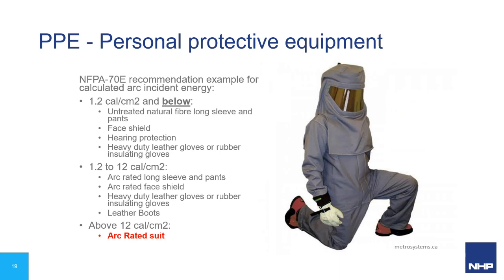And then above 12 calories per centimeter squared, it's talking about arc rated suits like what you've got on the right hand side there. Due to the comfort, the cost of the suit, and difficulty in carrying out the work while you're wearing the suit, there's a lot of reluctance around using these. Also, if somebody's asked to wear one of these, a lot of people aren't too keen to get into the sort of work where they have to wear something like this to do their job. It's a pretty difficult one to work with.